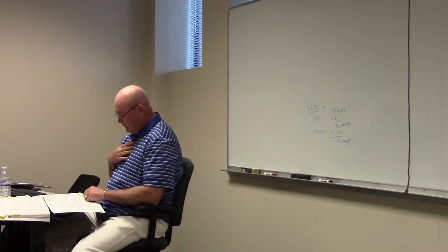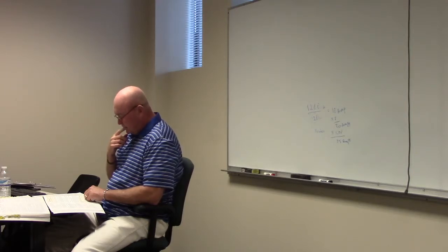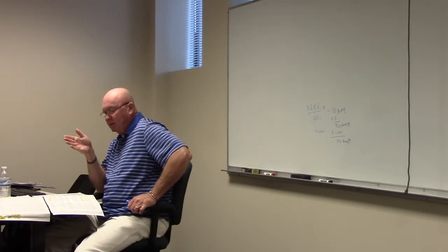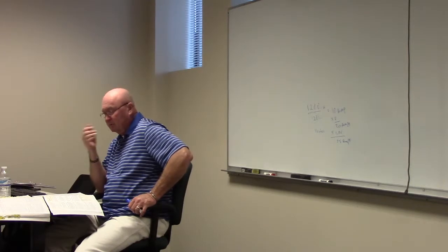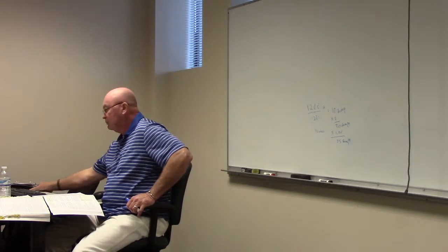Then select the single demand factor from the column that applies to the total computed load. Again, it says total computed load. Multiply the load by that factor to obtain the total demand for sizing the primary feeder or service conductors. So it's just another way of doing it without having to go through all the steps that we just went through. So that's loads for a restaurant.